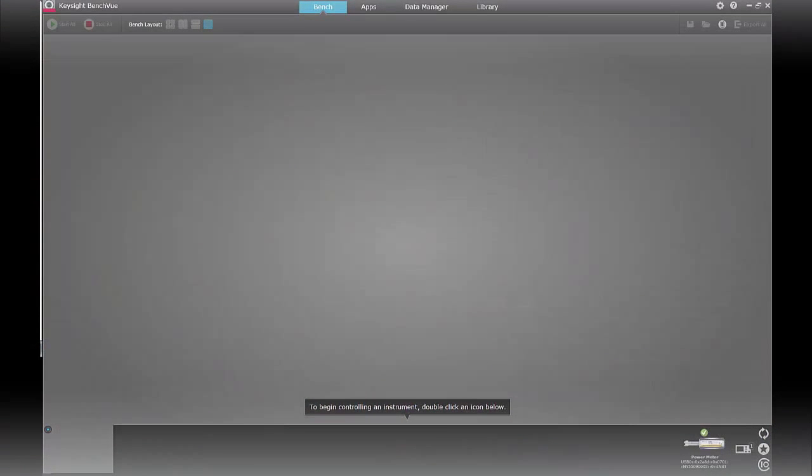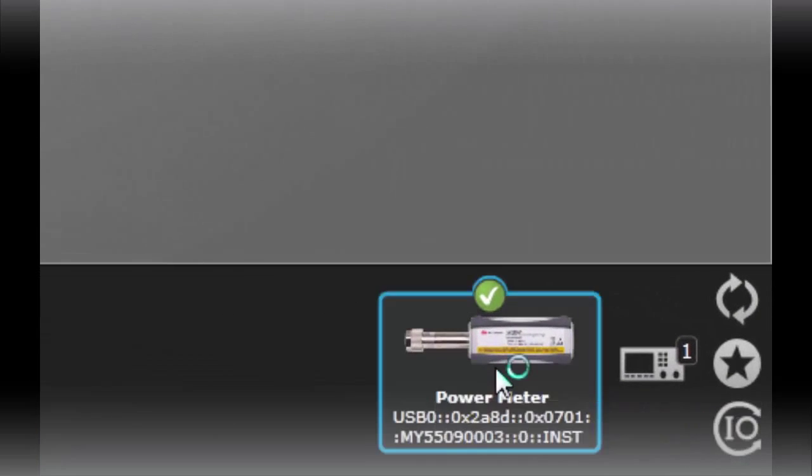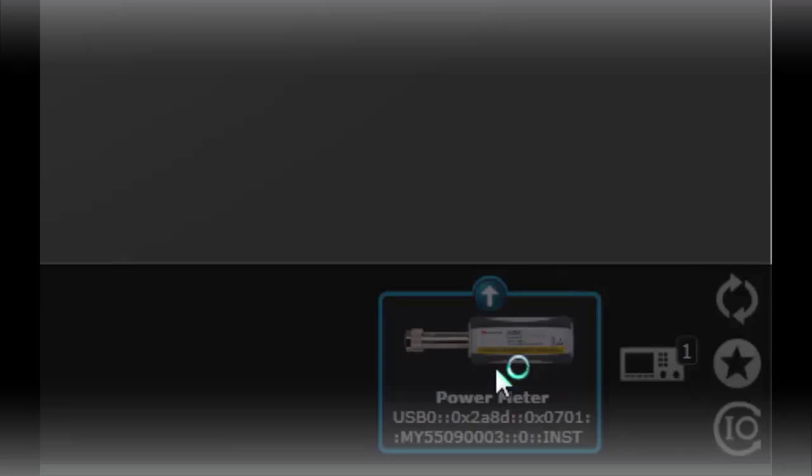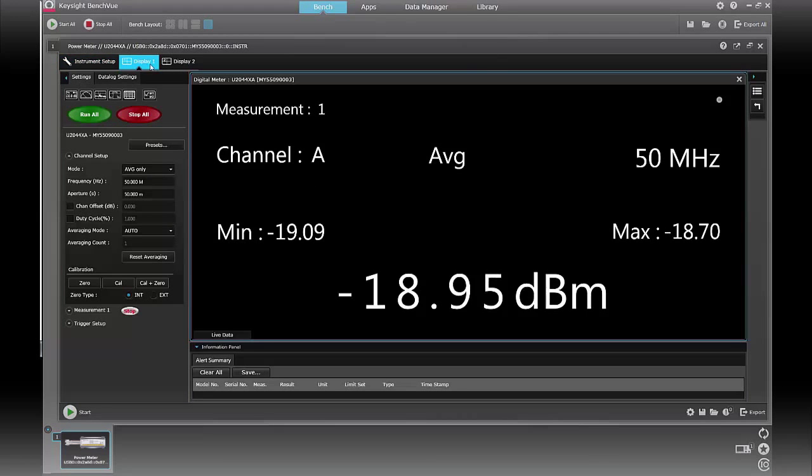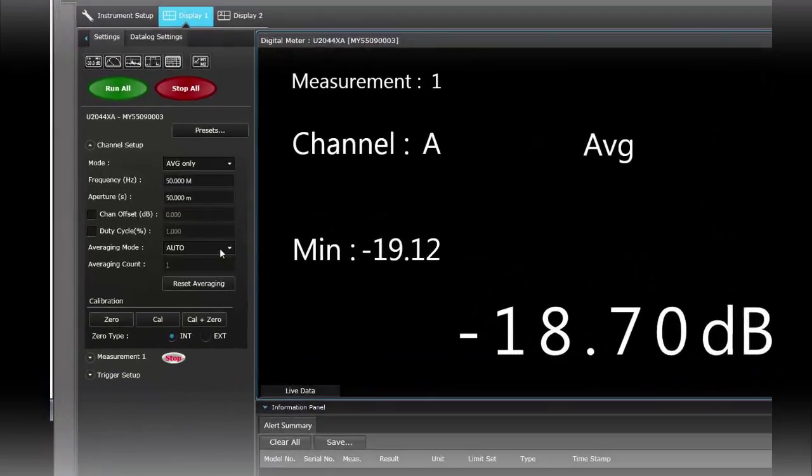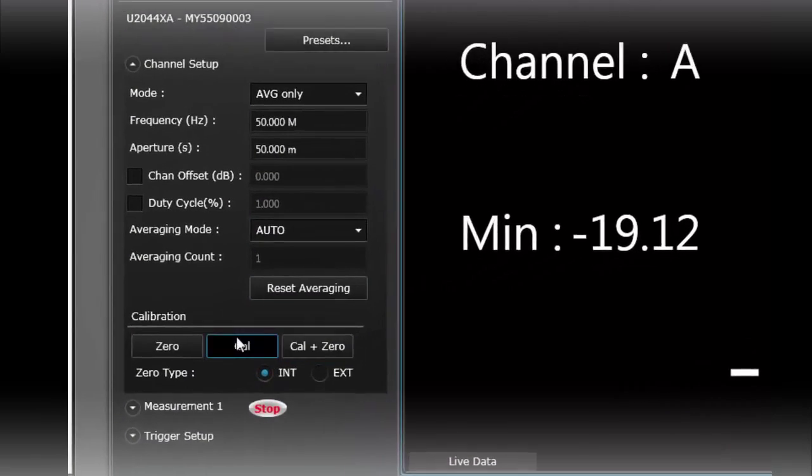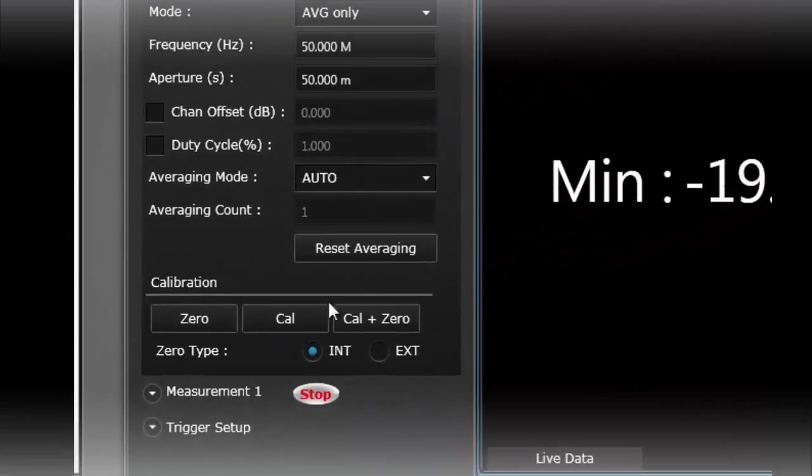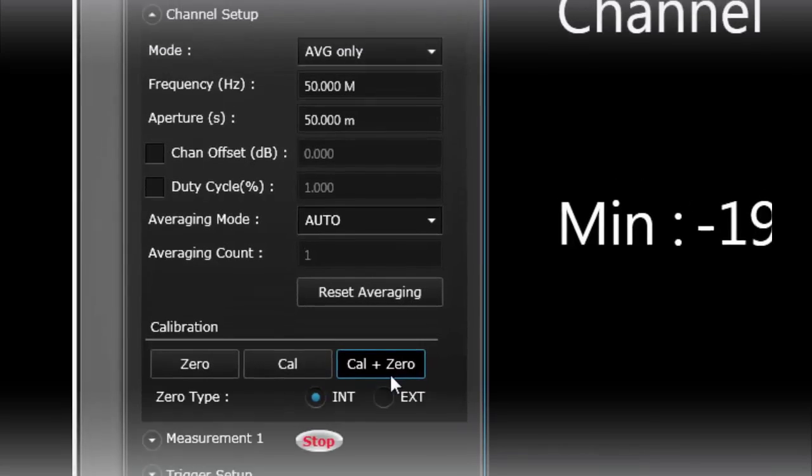So within BenchView on my PC now I have already found the power meter. I'm going to double click that to get that started again. And in the display one settings menu you see some basic configuration which we covered in the basic video. Again calibration is also always important so try to do your cal plus zero before you do your critical measurements.